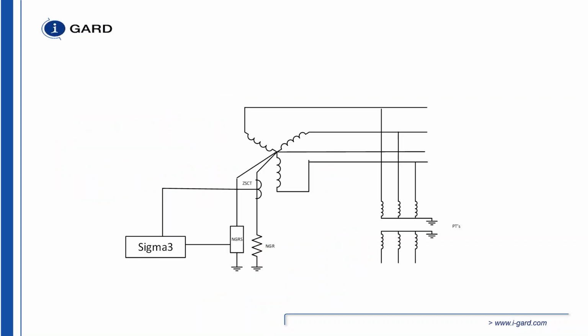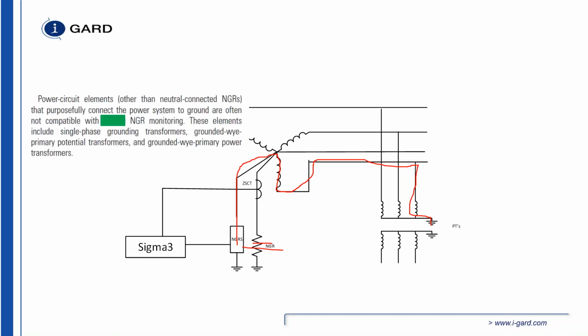The other thing they say is that where we've had issues, especially with the old way that we've had to monitor the integrity of the resistor, is if there are YY connected PTs. If there are YY connected PTs, obviously injecting a DC current, the problem is that there is such a low impedance that we can say the path of the resistor is good even if the resistor is open, because the DC impedance of this path is going to be very, very, very low. So using YY connected PTs with the old method of determining the integrity of the resistor, and some of my competitors' methods, is not very good.